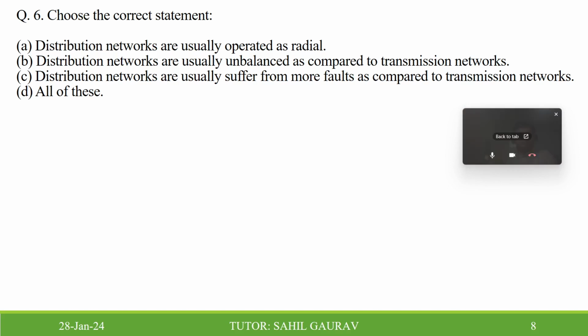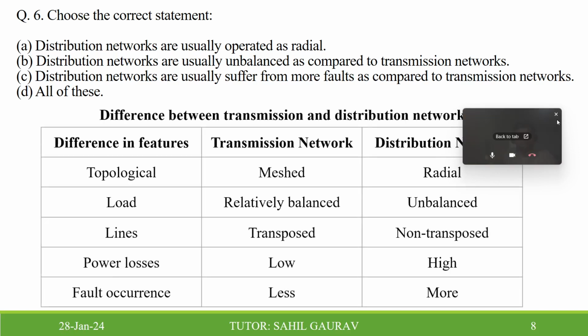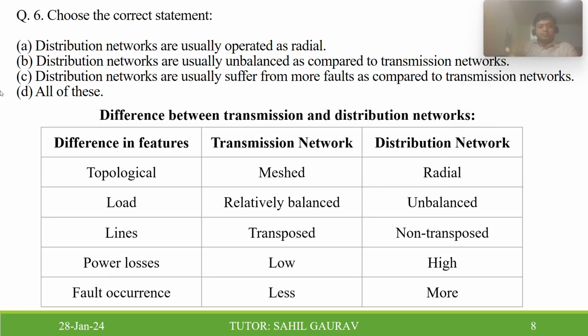Yeah, D is correct. Distribution networks are usually operated as radial. They are radial in nature, so the first is correct. And distribution networks are usually unbalanced compared to transmission networks. And distribution networks usually suffer more faults than transmission networks. We can see from the table that fault occurrence in distribution networks is higher. So all three above are correct, and D is the correct option: all of these. So a distribution network is radial in nature. You have to keep in mind these are unbalanced, non-transposed, and power loss is higher due to the high R/X ratio.